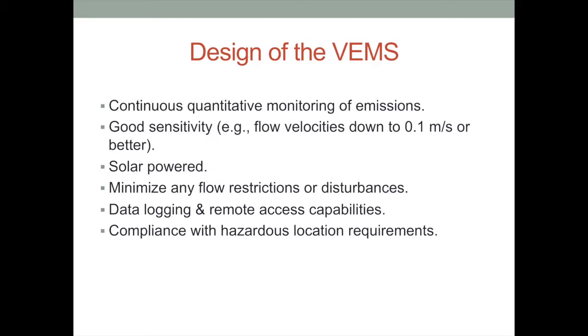The vent emission monitoring system put on the underground tank — and essentially the same capabilities are on the above-ground tank — has the objective of continuously quantifying the emissions coming off these tanks with as good accuracy as we could achieve. With the ultrasonic flow meter, we're able to get down to vent gas flow rates of about 0.1 meters per second or better.